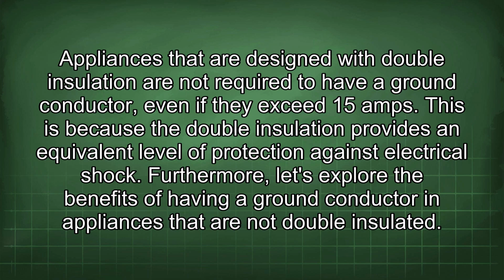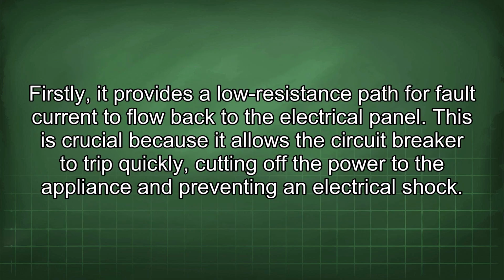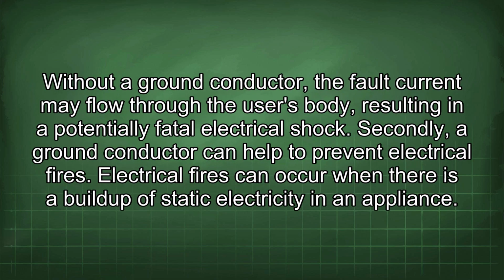Furthermore, let's explore the benefits of having a ground conductor in appliances that are not double insulated. Firstly, it provides a low resistance path for fault current to flow back to the electrical panel. This is crucial because it allows the circuit breaker to trip quickly, cutting off the power to the appliance and preventing an electrical shock. Without a ground conductor, the fault current may flow through the user's body, resulting in a potentially fatal electrical shock. Secondly, a ground conductor can help to prevent electrical fires.